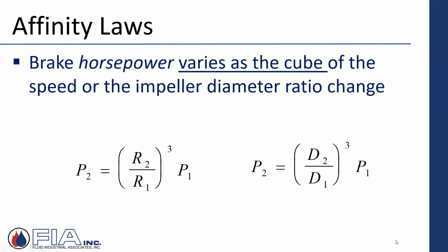And the last one would be the required horsepower. The brake horsepower varies as a cube, which is really why, from an energy savings standpoint, that's what has been driving variable speed, and why it has made so much sense for years and years, to the point where nowadays utilities even have some pretty aggressive VFD incentives for commercial customers that maybe have some older equipment still out there, pumps or what have you, that don't have a drive.